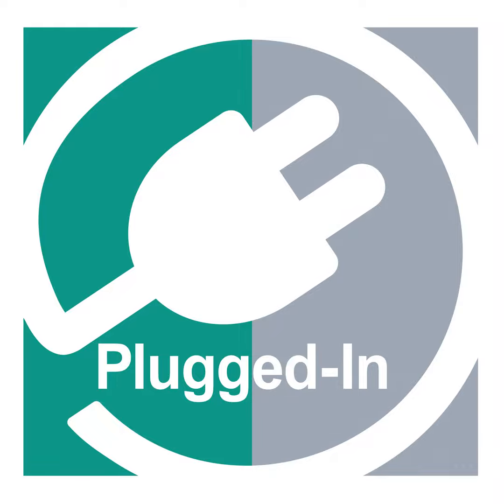All right, very good. And number 5, last one. What do you think is the number 5? Last one is we have an advanced temperature compensation. Okay, what makes it advanced? Sound waves depend on the temperature. Or better said, the speed of the sound depends on temperature. So when you have an ultrasonic sensor that uses ultrasound, you have to take into account the ambient temperature. That's what almost every ultrasonic sensor does to have precise measurements. But what happens if you power up your sensor? The sensor gets warm. Yeah. So during that power up phase, your measurements will drift a little bit. And in some cases, you need to wait 5 to up to 20 minutes, depending on the sensor, to have no more drift and precise and reliable measurement data.